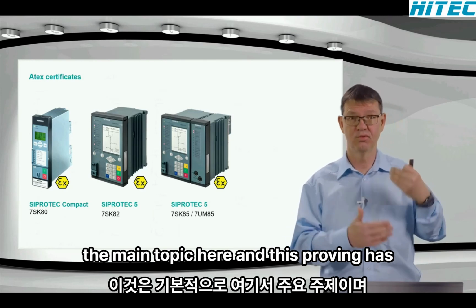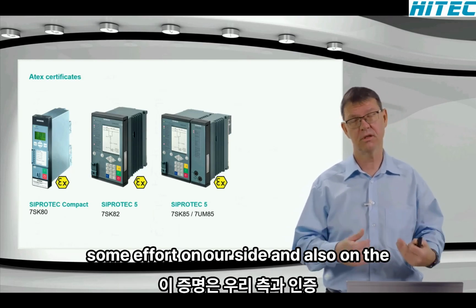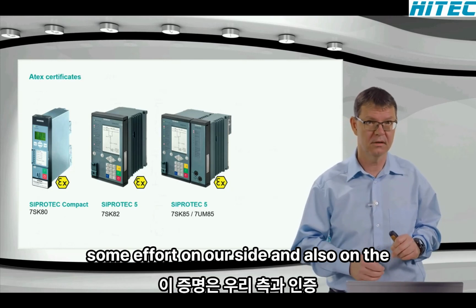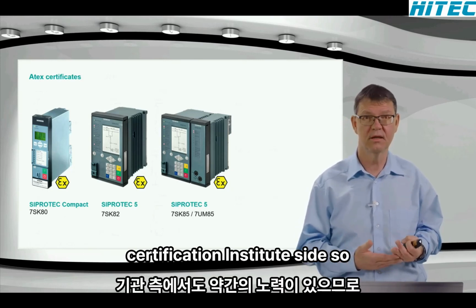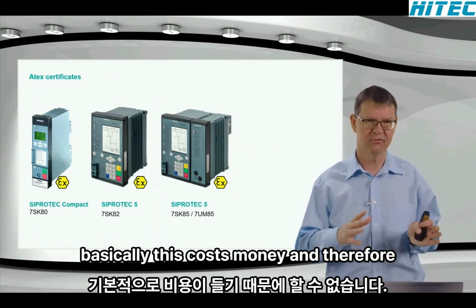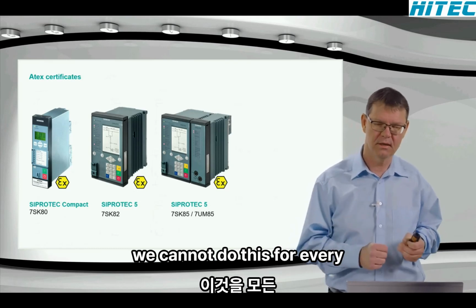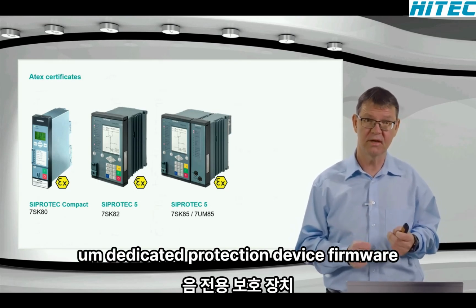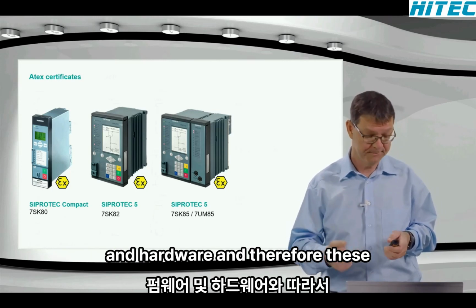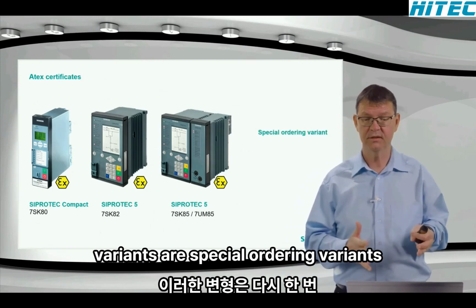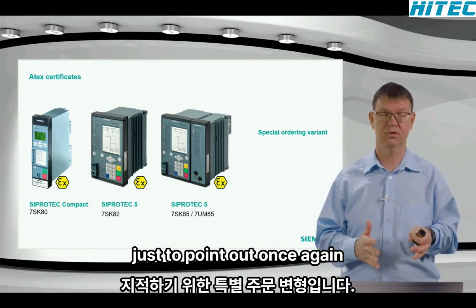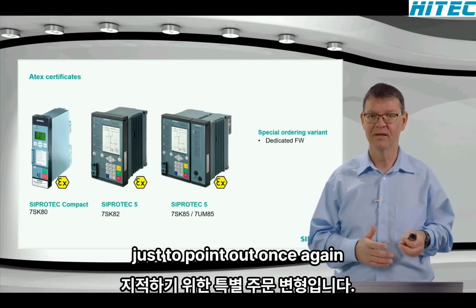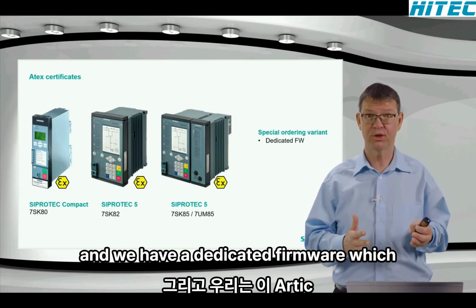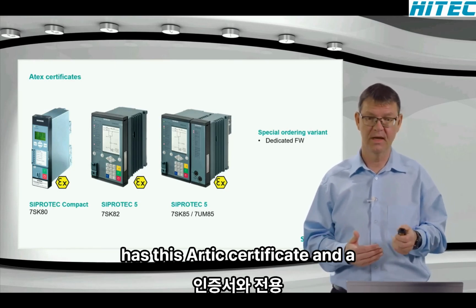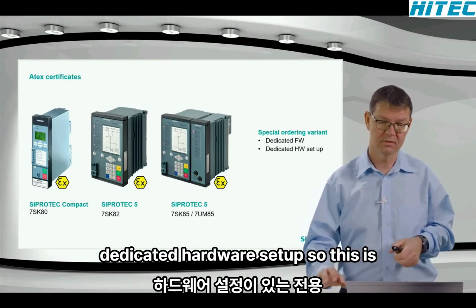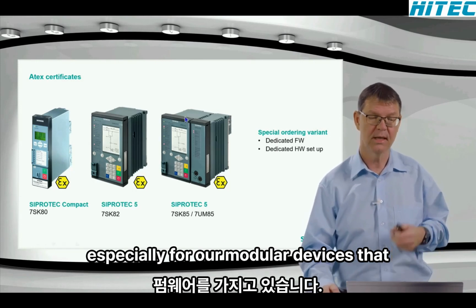And this proving has some effort on our side and also on the certification institute side. So basically this costs money, and therefore we cannot do this for every dedicated protection device, firmware and hardware. And therefore these variants are special ordering variants, just to point it out once again. And we have a dedicated firmware which has this ATEX certificate and a dedicated hardware setup. So this is especially for our modular devices.